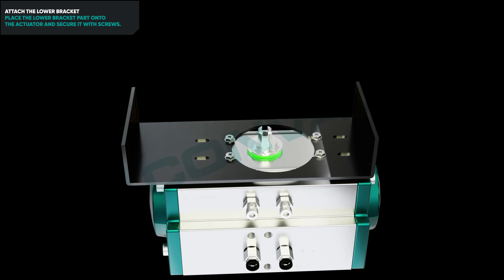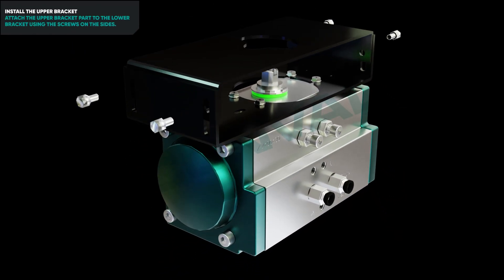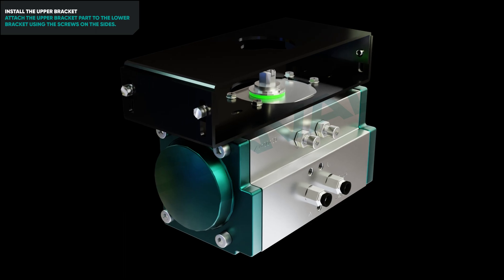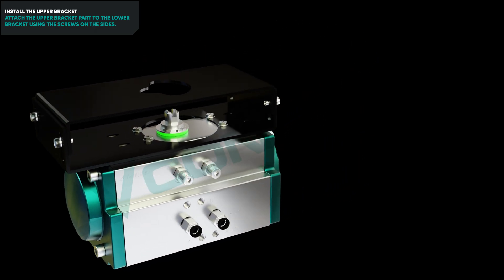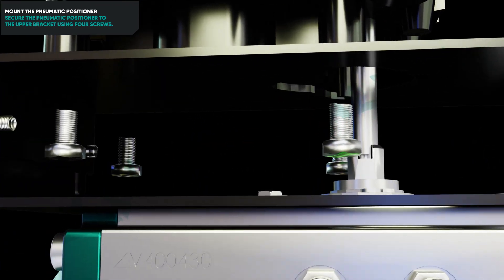Place the lower bracket part onto the actuator and secure it with screws. Attach the upper bracket part to the lower bracket using the screws on the sides. Secure the pneumatic positioner to the upper bracket using four screws.